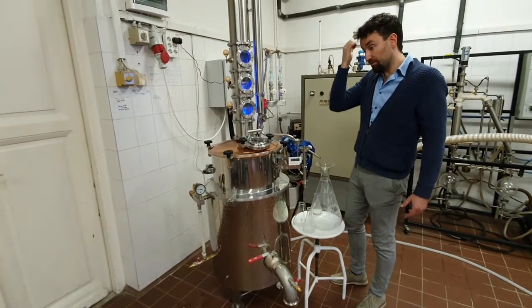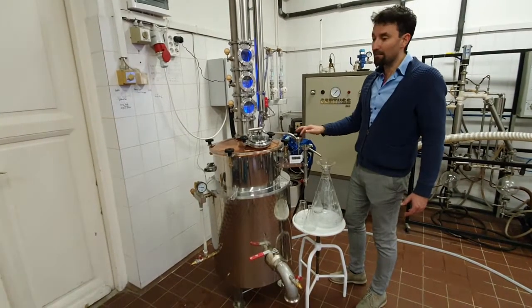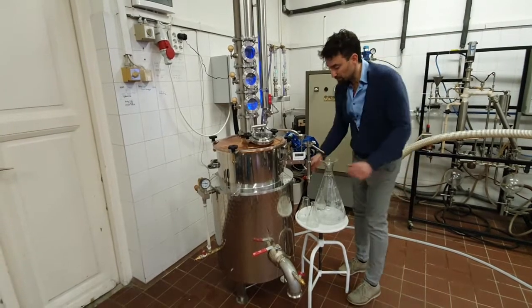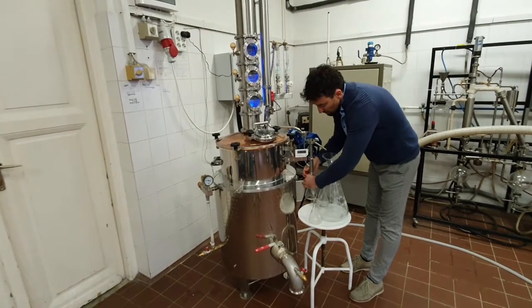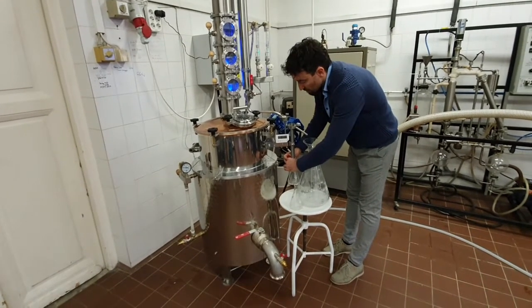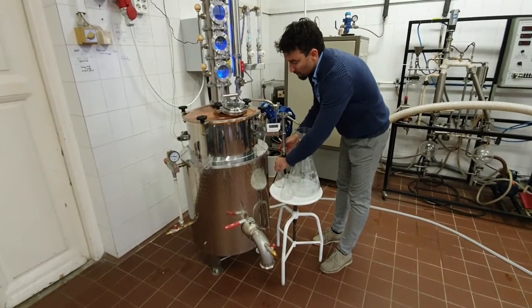We check the system again: heating is at 4 kilowatts, dephlegmator flow rate is between 30 to 40 liters per hour, final condenser flow rate is between 20 to 30 liters per hour. The thermometer of the final condenser should stay between 40 to 60 degrees Celsius during the whole distillation.